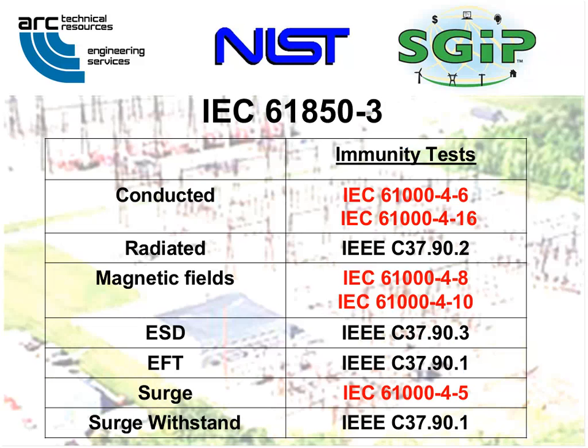IEC 61850-3 only addressed products used inside the substation fence, and it required these immunity tests shown on the right. 61000-4-6 is conducted RF immunity up to 30 megahertz. We don't use radiated testing for those long, low frequencies like the hams do with those huge antennas. We do this as a conducted test because it's easier to do the test, and the signal levels are more consistently delivered.